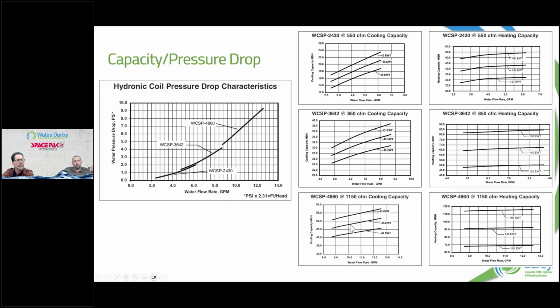So these are pretty cool because they don't lie, right? They're going to tell you if I flow 7 GPM at this water temp, I'm getting X amount of BTUs. I think this is where we introduce some components we're maybe not familiar with, like circuit setters and stuff like that, where we can really dial in how many GPM we're doing, dialing into BTUs. I had a project where we had some air handlers, and it just wasn't something that was put into design.